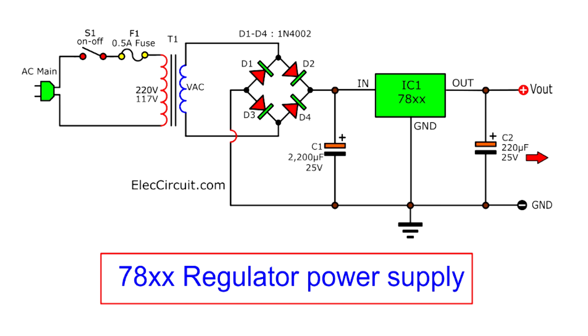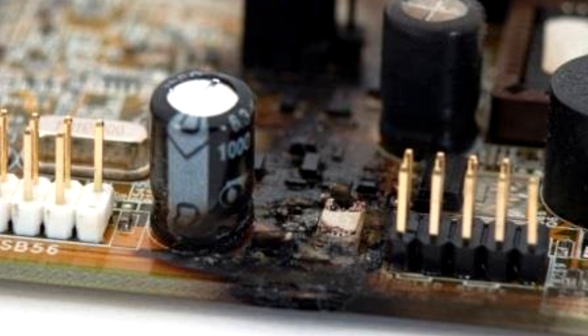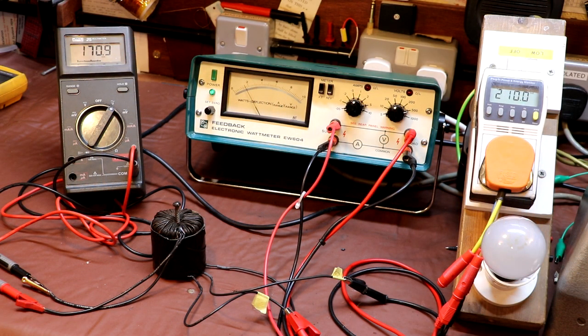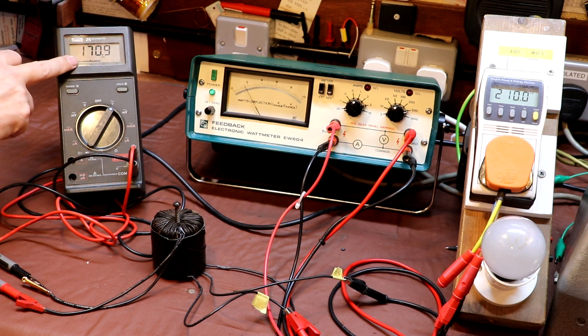Now, in most cases with modern equipment, we've probably got a voltage regulator, but you can still come unstuck, because if you have very poor regulation, you could pull the output voltage of the secondary below the voltage at which the regulator will work. You can also have the opposite effect: if for some reason you stop loading the transformer and the voltage rises, you wouldn't want it to rise to a point where it might damage your equipment. The test for voltage regulation is very easy to do, and quite an interesting one. All we have to do is measure the secondary voltage of the transformer unloaded, with no load on the transformer, and we can see it's outputting 170 volts at the moment.